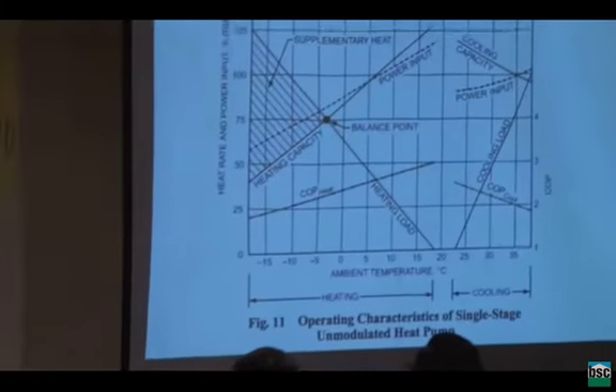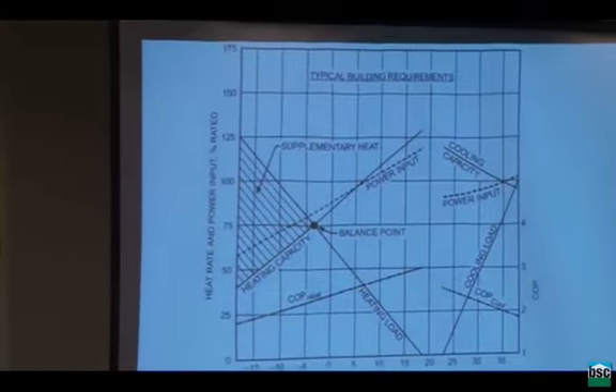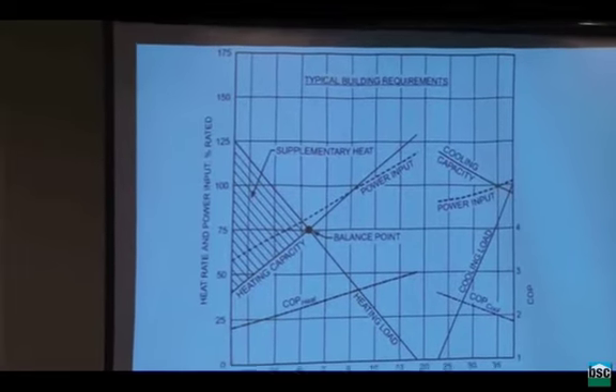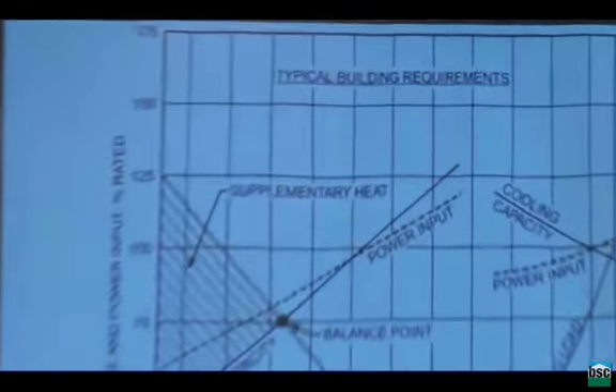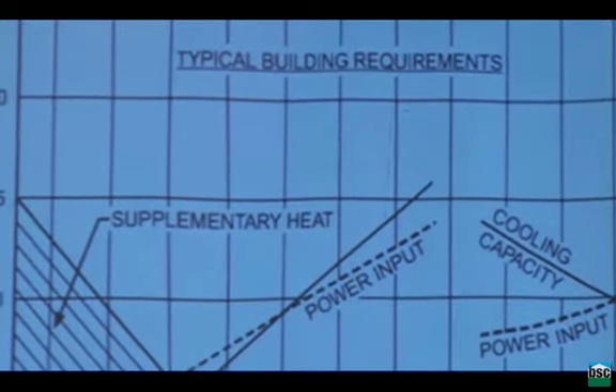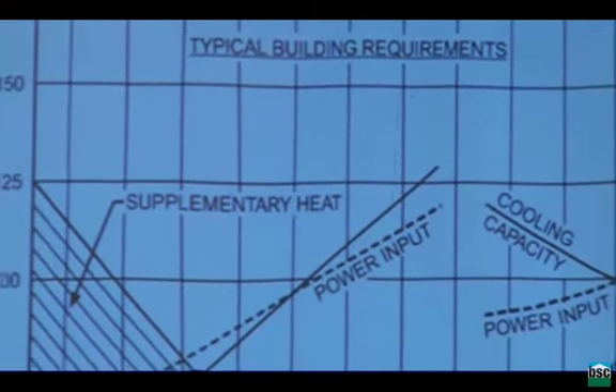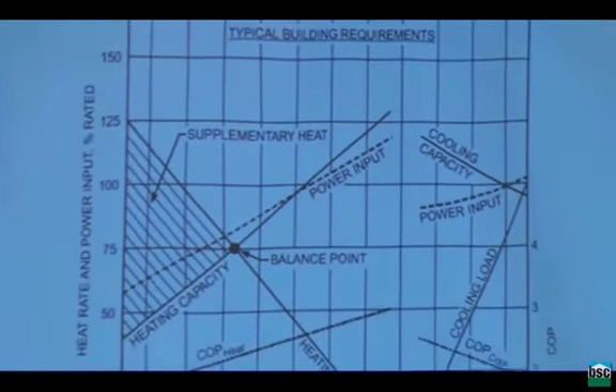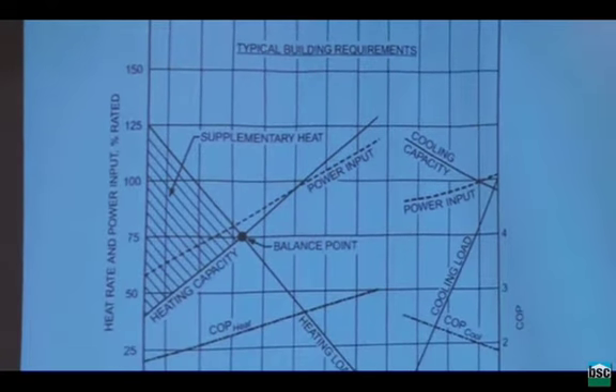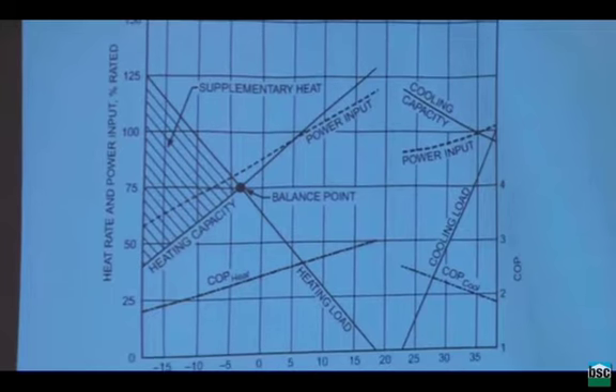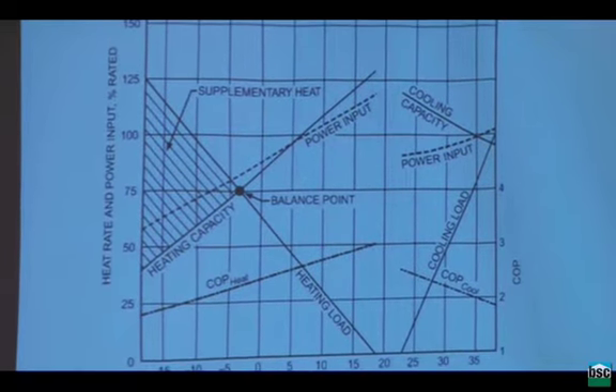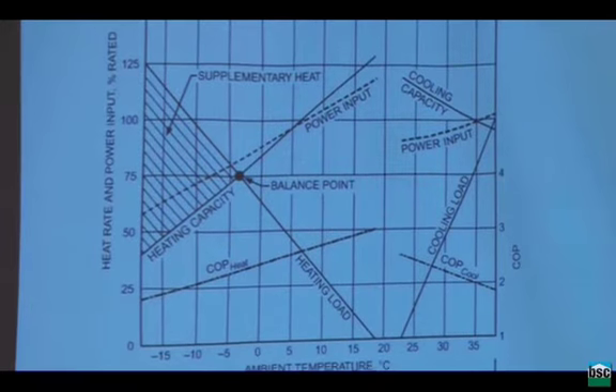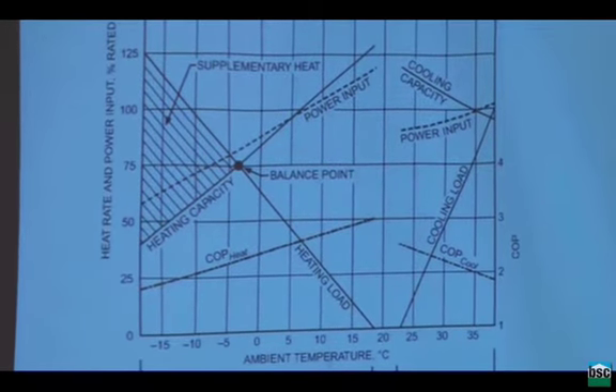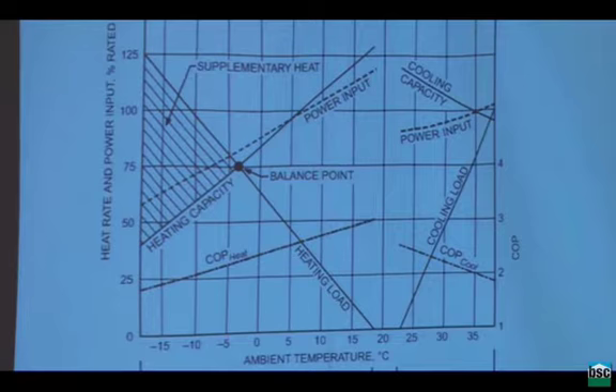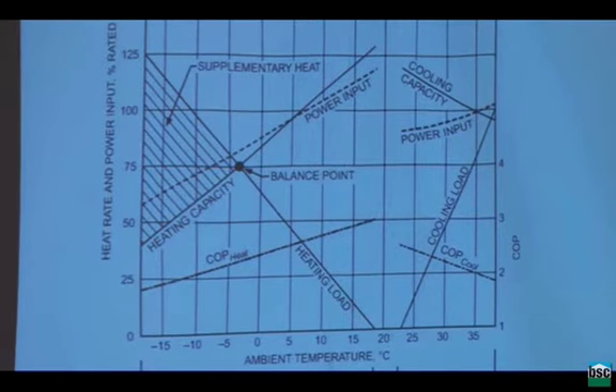So here's another one of my simple and easy to understand graphs, which shows how one would normally look at a single-speed, off-the-shelf Carrier, Trane, Goodman, Lennox, Rheem, whatever, heat pump. And the temperature outdoors is in degrees Celsius, so 20 degrees, 68 Fahrenheit. The assumption is that heating begins at 65 degrees Fahrenheit and increases linearly from there. That's what the line on the left, sloping upwards, says is heating load. As it gets colder, you have to provide more heating.